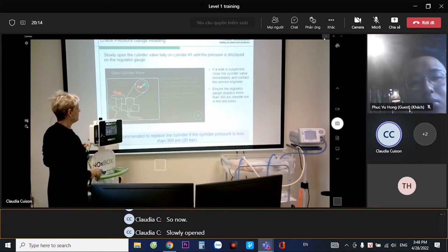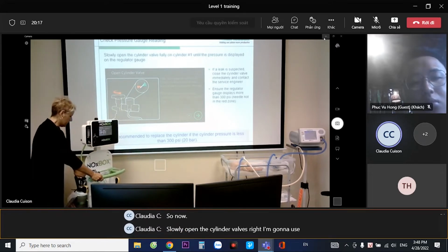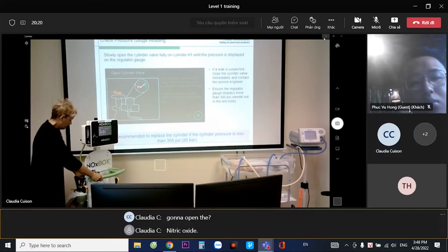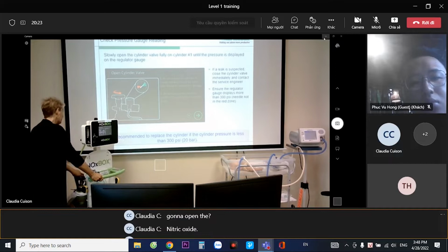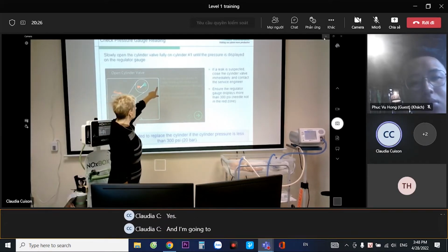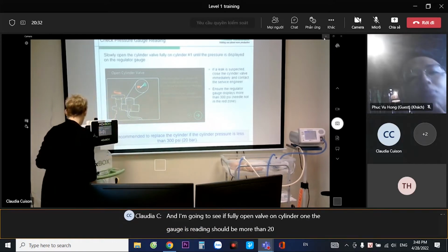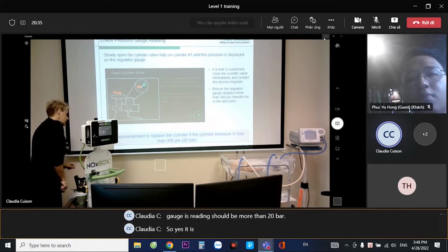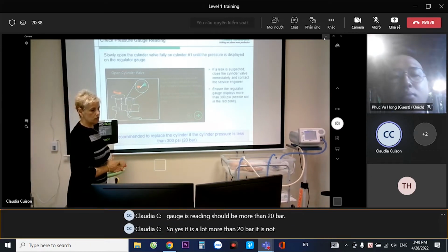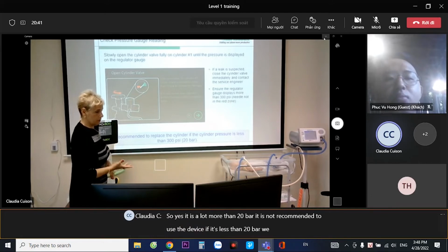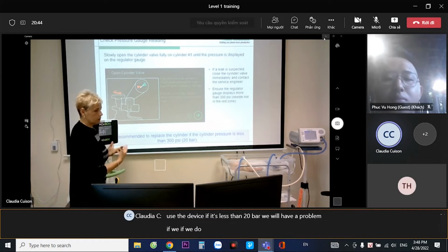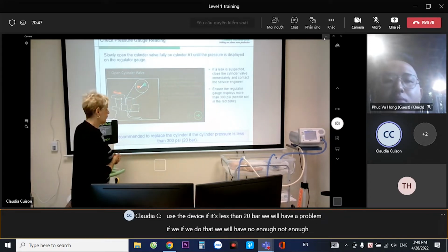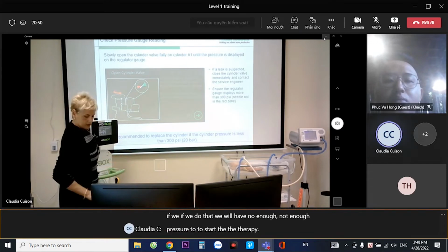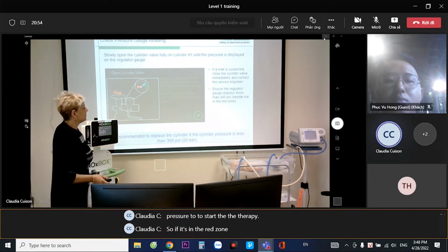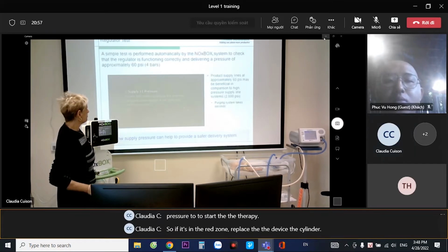So now, slowly open the cylinder valve, right? I'm gonna open the nitric oxide gas, and I'm going to see if fully open valve on cylinder 1, the gauge reading should be more than 20 bar. So yes, it is a lot more than 20 bar. It is not recommended to use the device if it's less than 20 bar. We will have a problem if we do that. We will not have enough pressure to start the therapy. So if it's in the red zone, replace the cylinder.